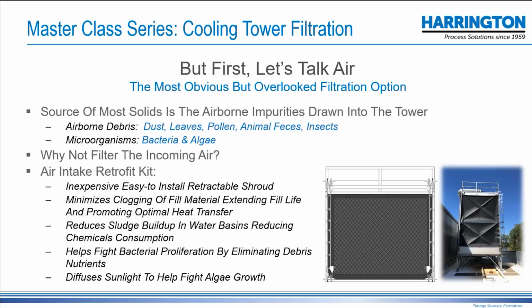As I said, there's a huge volume of air going into the cooling tower that's laden with all kinds of debris, solids, dust, and other contaminants. Well, if you screen it out before it even gets into the cooling tower, then of course you're going to deal with a lot of it at the air level, not at the water level. And so there are screens basically designed for cooling towers that can be retracted up and down, and they will be a first line of defense to keep dirt from getting into the cooling tower.